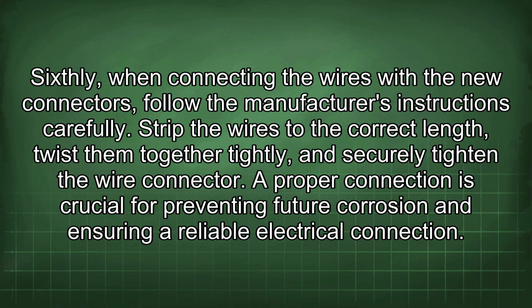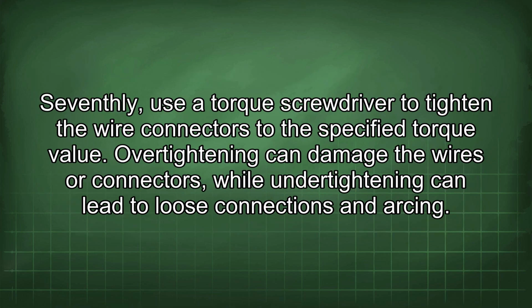Sixthly, when connecting the wires with the new connectors, follow the manufacturer's instructions carefully. Strip the wires to the correct length, twist them together tightly, and securely tighten the wire connector. A proper connection is crucial for preventing future corrosion and ensuring a reliable electrical connection. Seventhly, use a torque screwdriver to tighten the wire connectors to the specified torque value. Over-tightening can damage the wires or connectors, while under-tightening can lead to loose connections and arcing.